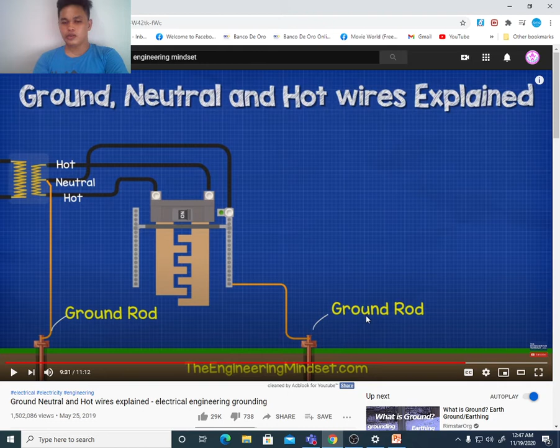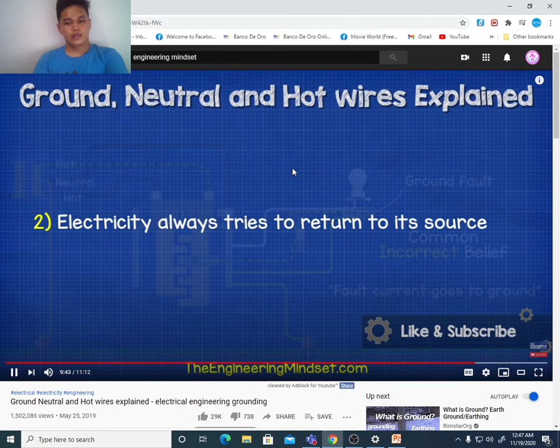Many people think that during a ground fault, electricity flows through the ground rod and into the earth. But remember, electricity tries to get back to its source. It doesn't just go into the earth. And as there is a ground rod at the transformer, then there is a potential path for the electricity to get back to the source. But this path will have...